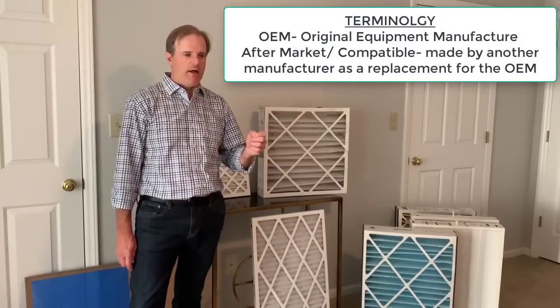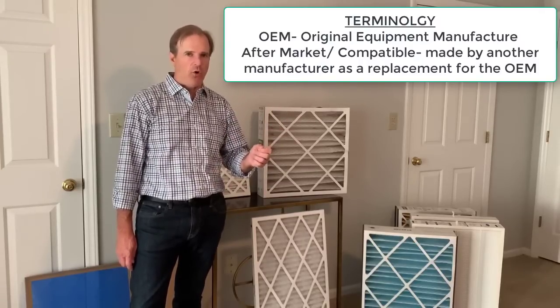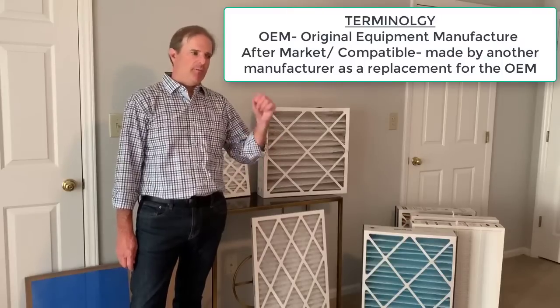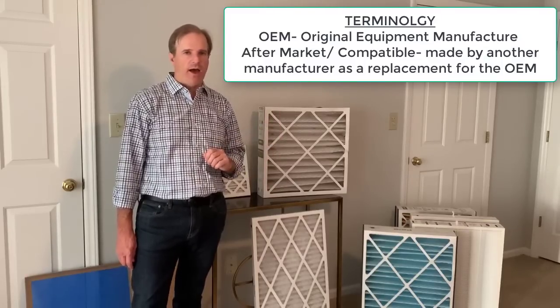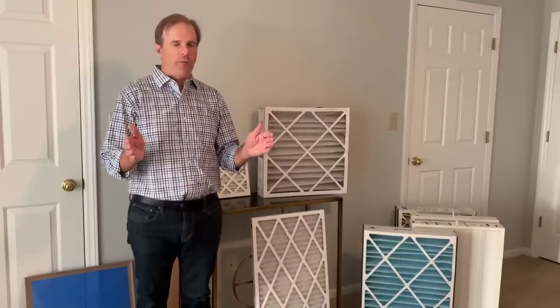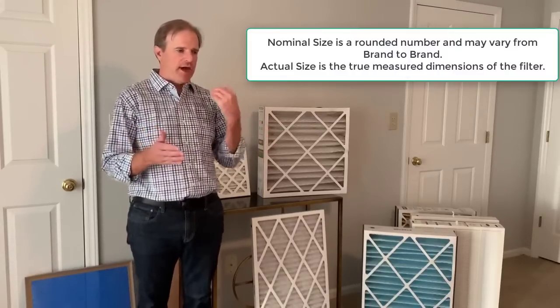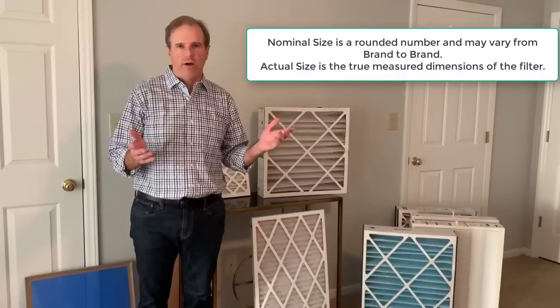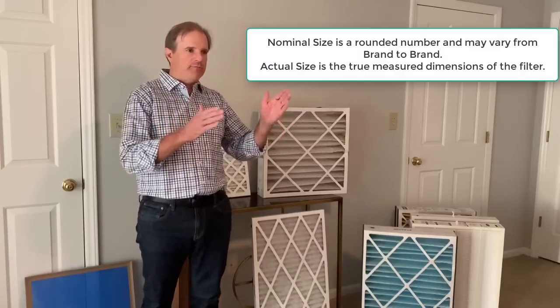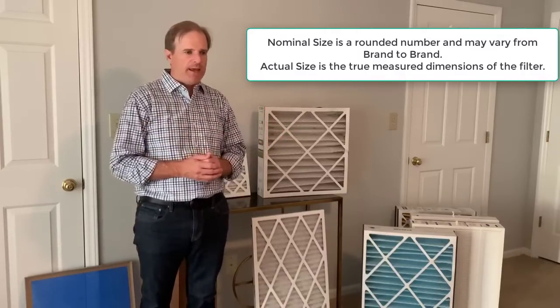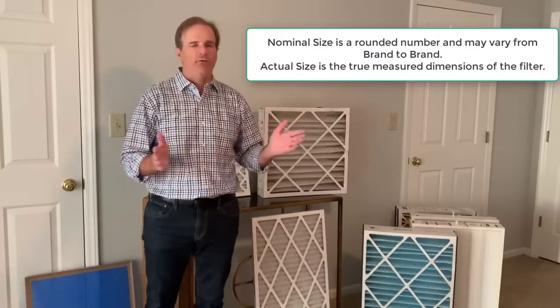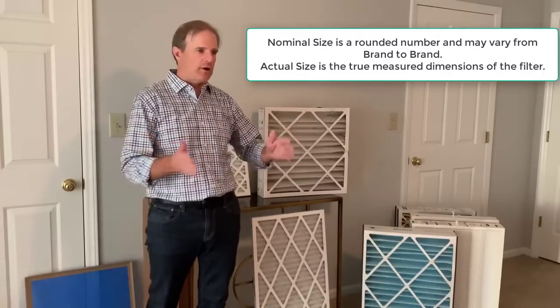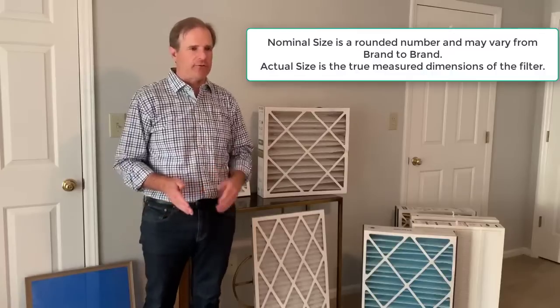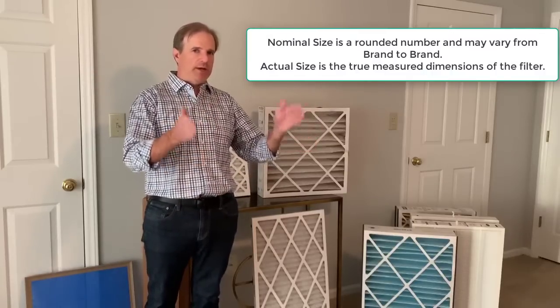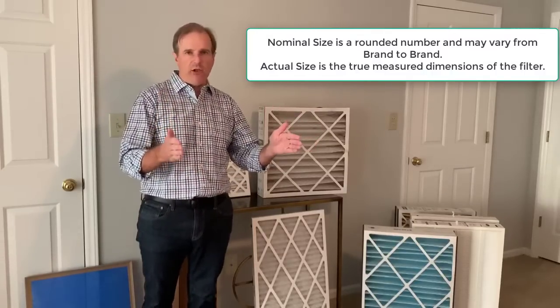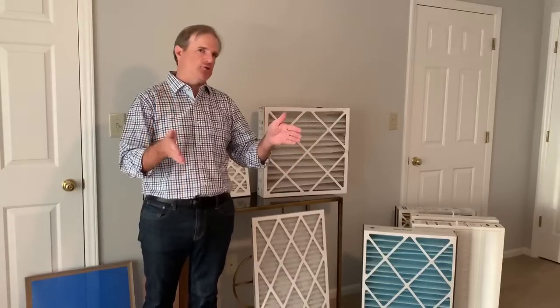So by knowing that if you get the correct compatible, you can save a lot of money, but you need to make sure that you have the correct size. So air filters are labeled by what's called the nominal size. So that means that it's a rounded number. The actual size of the filter may or may not be on the filter, and not all 20 by 25 by 5 filters are compatible from one manufacturer to the next. So you want to check for compatibility and size. And you can do that by looking at your filter and by measuring your filter.